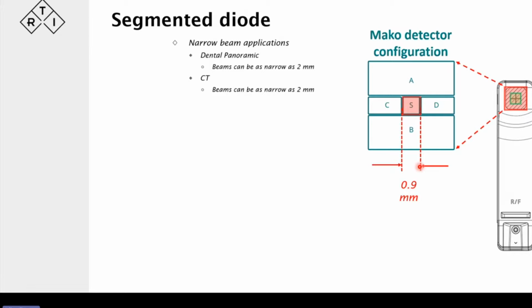Well, for instance, in a panoramic dental application, the beams can be as narrow as 2 or 2.5 millimeters wide. To get a proper dose reading, the detector itself needs to be fully irradiated, and in that small beam it needs to be smaller than 2 or 2.5 millimeters. This detector has a segment which is 0.9 millimeters wide, which, even for the narrowest of panoramic dental beams, will be fully irradiated. And this segmentation has some other benefits as well. We've got the possibility to read the value, the dose hitting segment C and segment D.